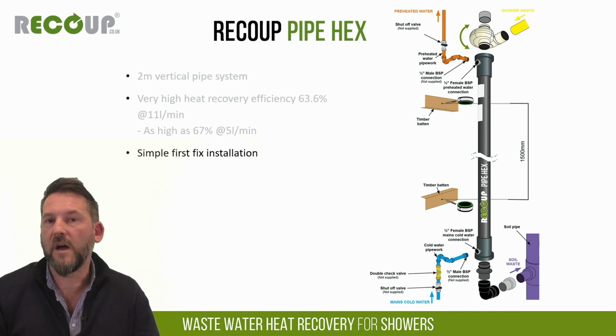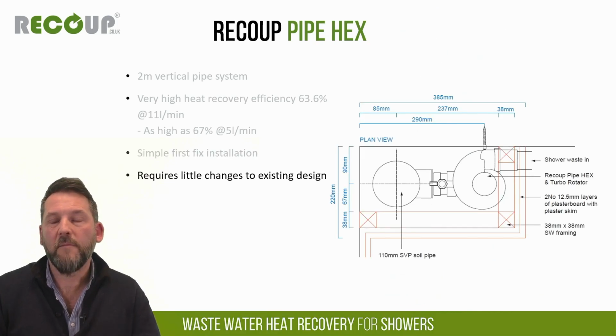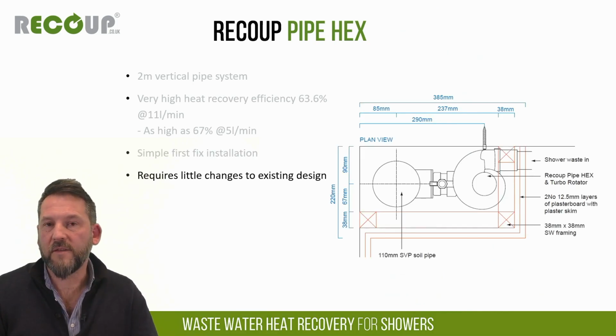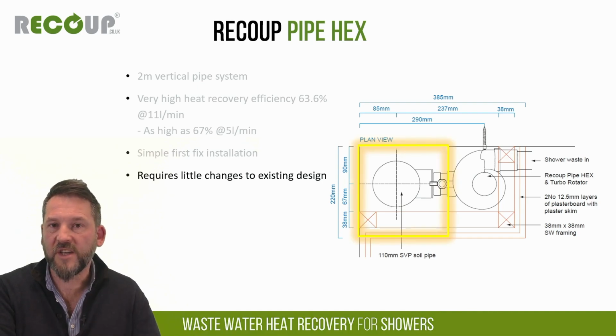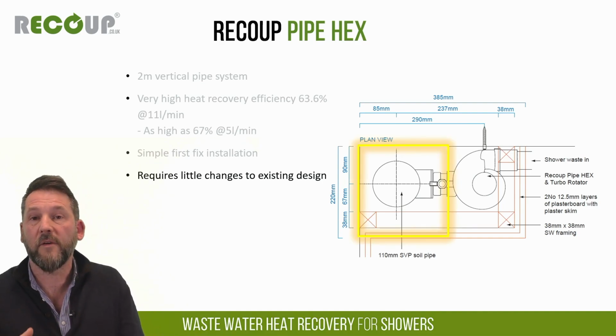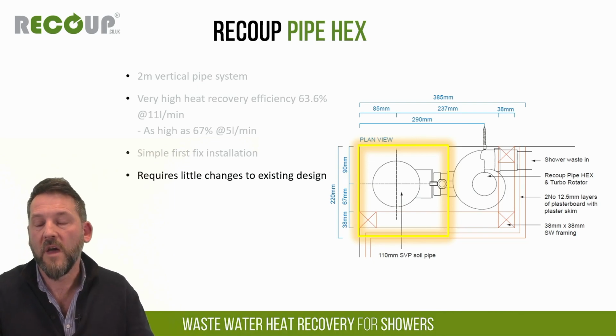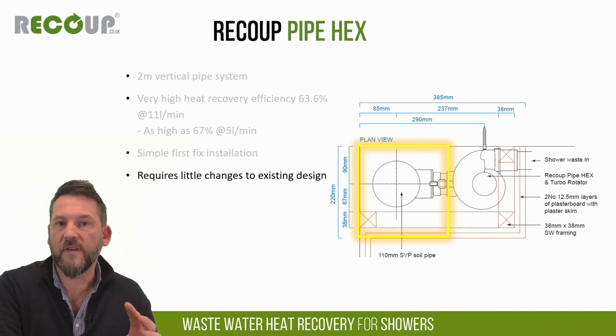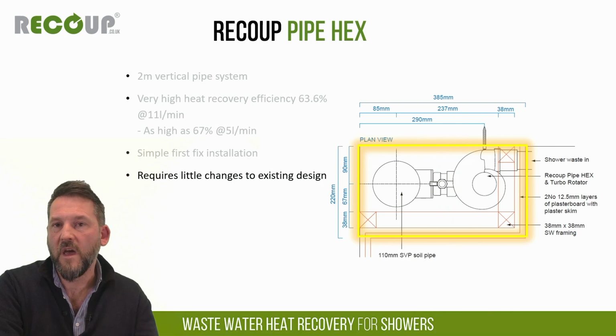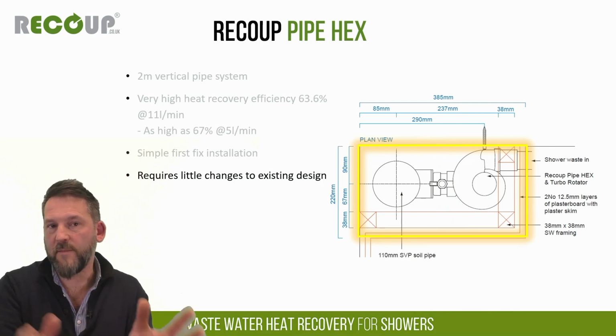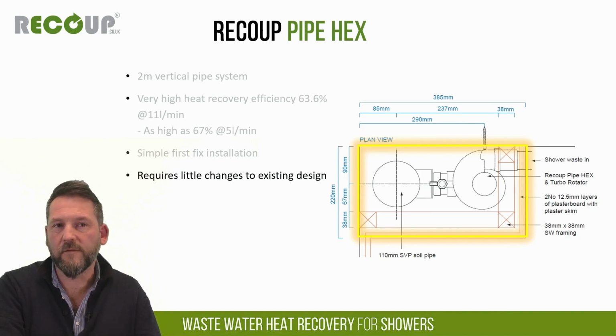So it really is a relatively simple, cheap and quick product to install at first fix. It also, as I said earlier, requires very little design changes to existing homes or takes up very little floor space in new build. So where we box in next to the SVP on the ground floor normally, your standard SVP boxing will be around about 220 by 220 mil normally. Wastewater heat recovery included will just add about 200 millimeters in one direction. So it really isn't taking up a great deal of floor space.